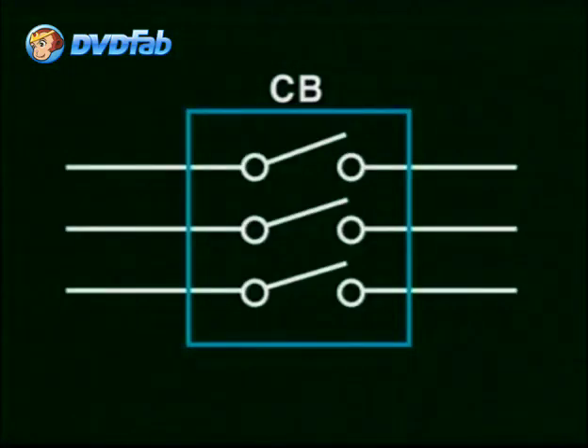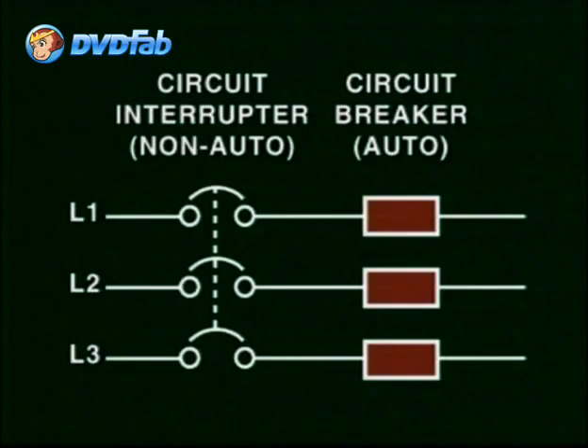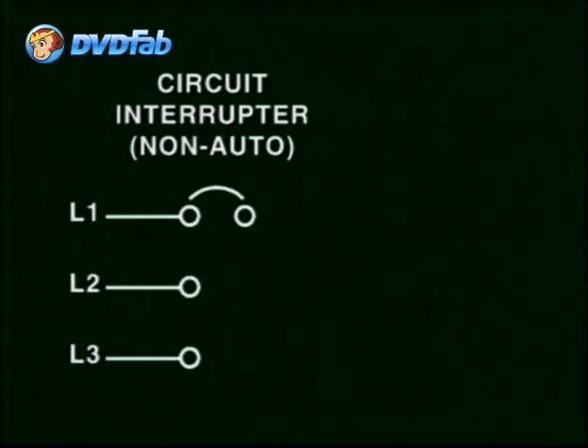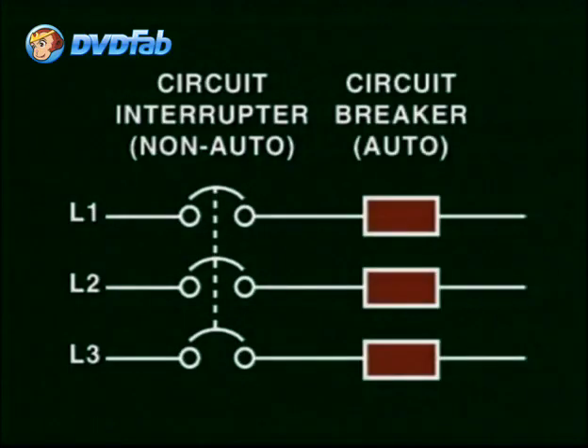A circuit breaker, as defined by NEMA, is a device that opens and closes a circuit by non-automatic means if used as a disconnect, or that opens the circuit automatically on a predetermined overcurrent created by an overload or a short circuit. The circuit breaker trips a mechanism inside which disconnects the circuit from the overcurrent condition. The basic part of a circuit breaker, namely a circuit interrupter, is represented by this symbol for a single-pole, two-pole, or a three-pole circuit. This section of the breaker, which is the non-automatic, is followed by the automatic breaker section representation.